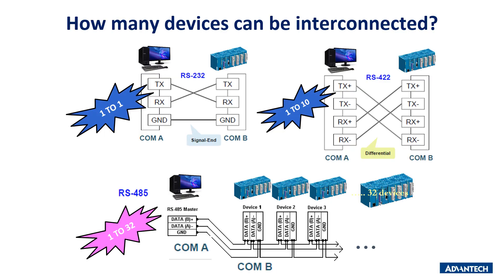How many devices can be interconnected on the same network? Each configuration has a limited number of devices. For RS-232 only one device can be connected to one host — inefficient for industrial environments with many machines. For RS-422, up to 10 devices can be connected to a host. RS-485 is the most popular because it supports 32 devices on a network.